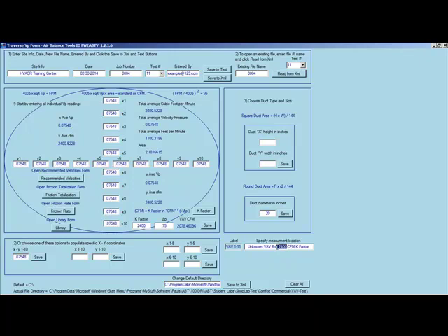We've recorded 2400 because the outlet of our VAV box was 0.0755, and at 0.0755 we saved that, and we populated both our X and Y axis, and this is a 20-inch duct, so we saved that and we came up with 2400 CFM. So now the K factor at 1 inch is 2400 CFM.